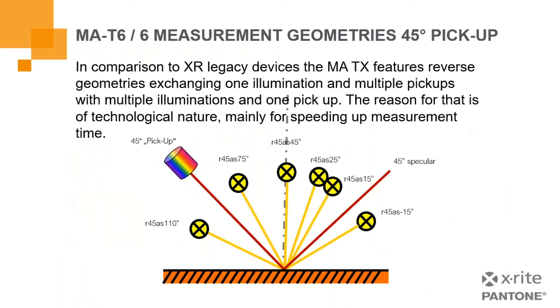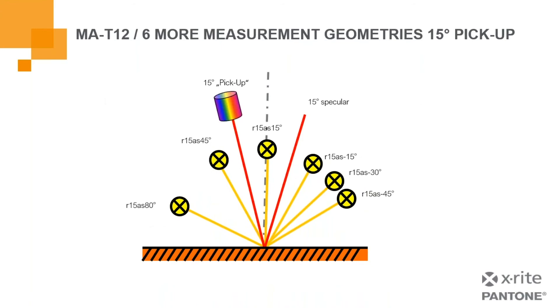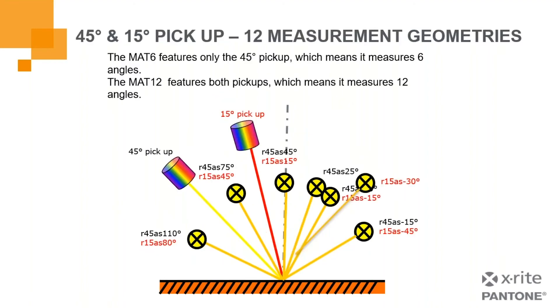The MAT6 instrument geometry uses a 45-degree pick-up. In comparison to X-Rite legacy devices, the MAT features reverse geometries exchanging one illumination for multiple pickups, versus multiple illuminations with one pickup — this speeds up measurement time, giving a more responsive measurement over our legacy instruments. With the MAT12, we add six more measurement geometries: everything from the MAT6 plus a second pickup and additional measurement geometries, allowing capture of higher-end texture and sparkle. To summarize: the MAT6 measures six angles at 45 degrees, and the MAT12 gives you 12 angles at both 45 and 15 degree pickup geometries.